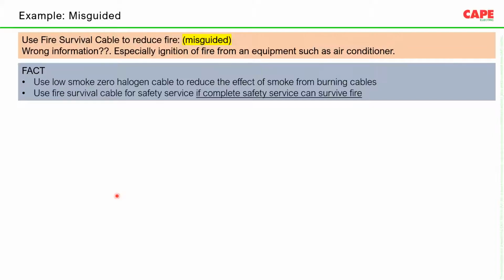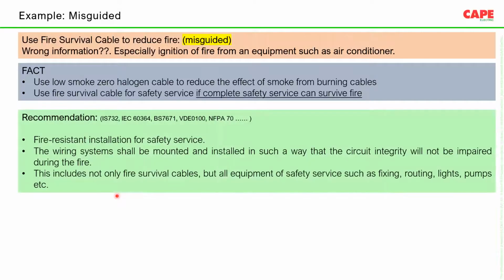So electrical installation, including the wire, the conduit, the screws, the fixing, the cable trays, the trunking, the light, the fan, the switch, the MCB, the distribution board, and everything. It is not only about wire alone. It is the complete electrical installation which is supposed to survive. But unfortunately, what happens in India is people think that fire survival is about wire and they keep on changing the wire.